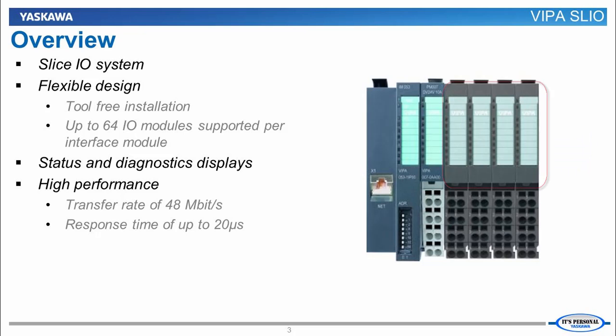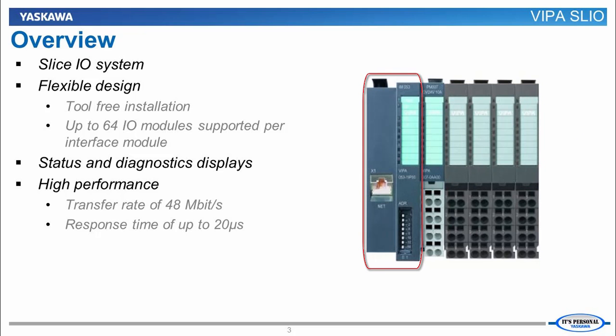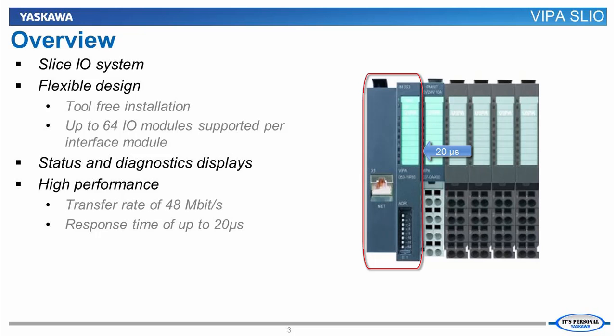Each SLICE shows the status of its input or output terminals along with its connection to the interface module. The interface module can transfer data between itself and the other modules at 48 megabits per second. The response time between the I.O. module and the interface module can be as low as 20 microseconds.